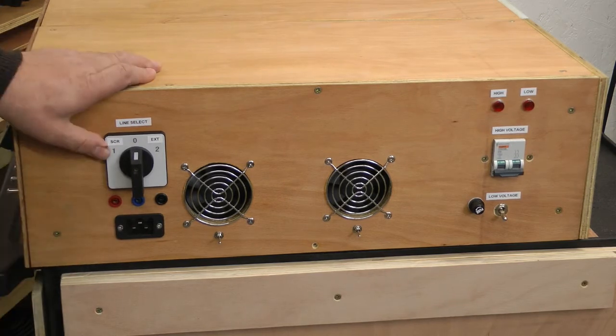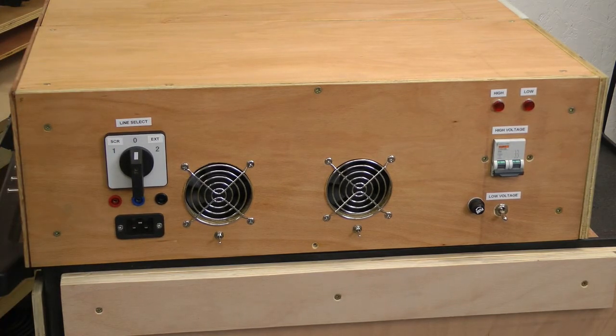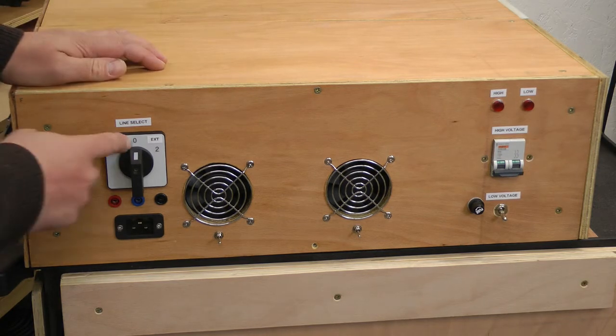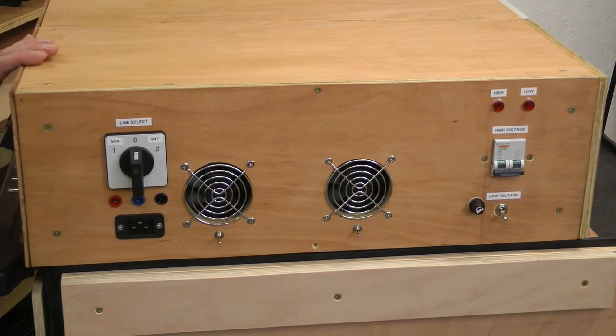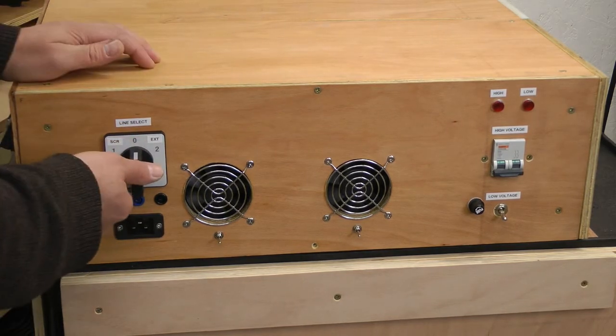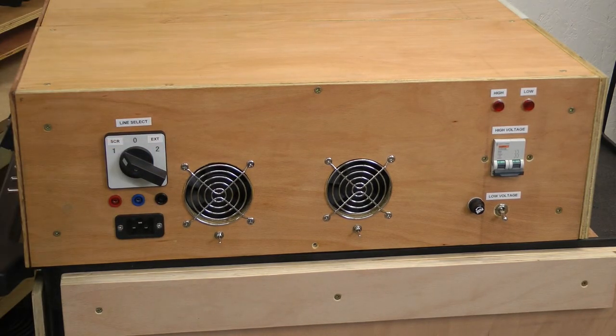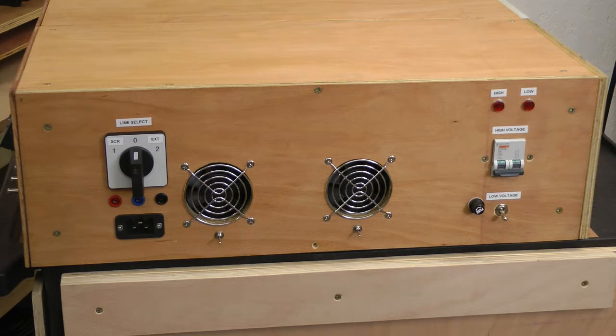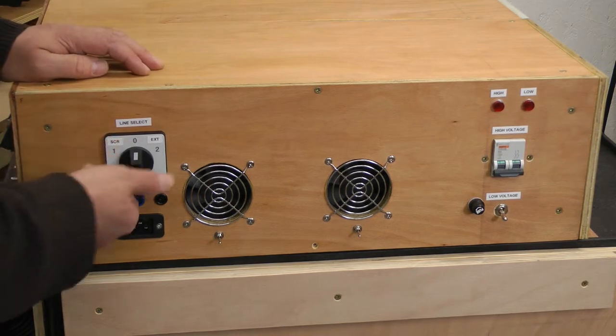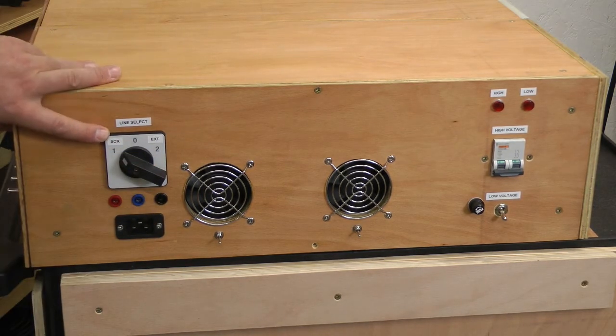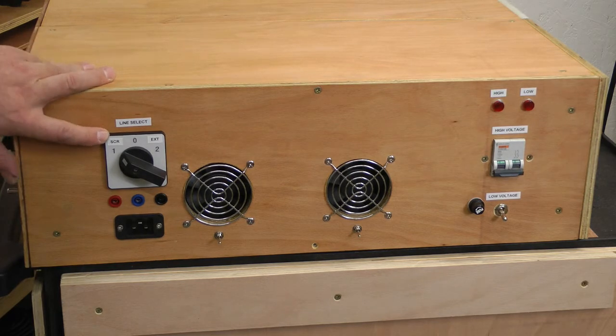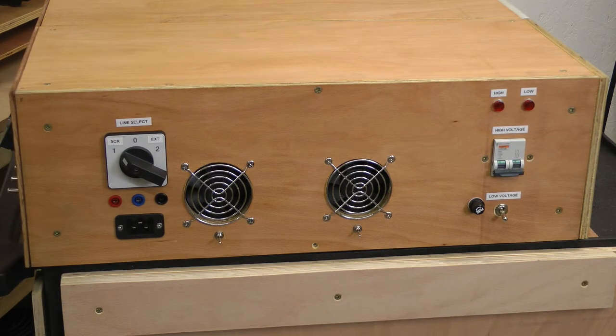Okay, so from here the power's come across to this now line selection switch. So here we're going to select where we can actually take mains power from. So at the moment it's off. So in other words, no power will be provided to the front panel. This is particularly useful in operation when you actually want to move the system to no power or turn it all off in one go. The switch there will turn off all control to the transformers. Now we've got two other settings. So off there, that is the SCR. So the SCR is the internal power controller and is controllable by the controls on the front and also from the remote control.